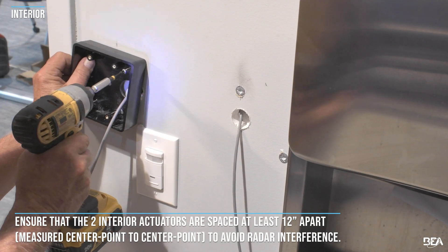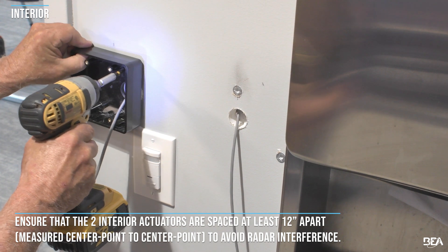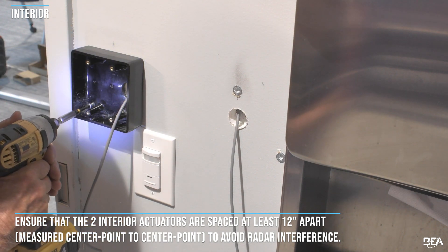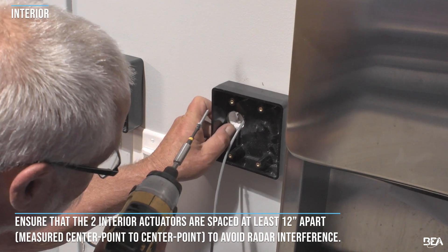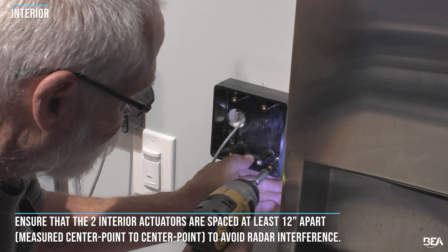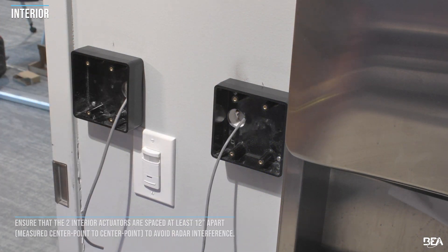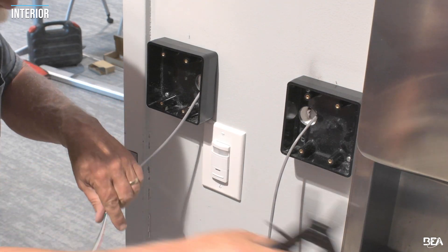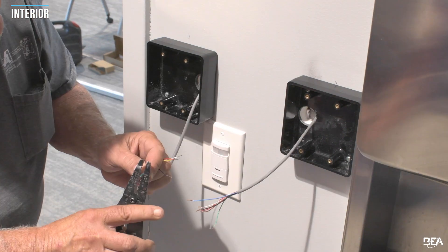Ensure that the two interior actuators are spaced at least 12 inches apart, measured center point to center point, to avoid radar interference. Install the mounting box using the pilot hole locations. Do not drill outside of the pilot hole locations. If a wire conduit is required, you may also use any of the pilot hole locations. To achieve an IP65 rating, you must apply silicone to any drilled holes.